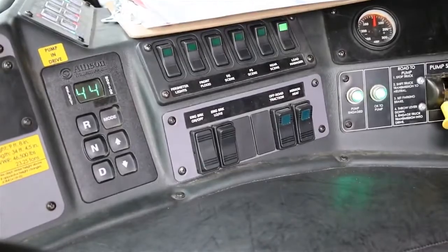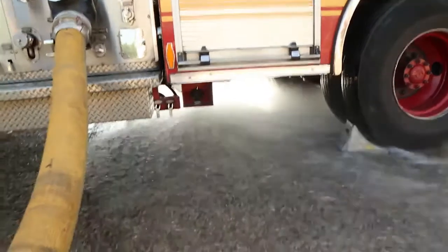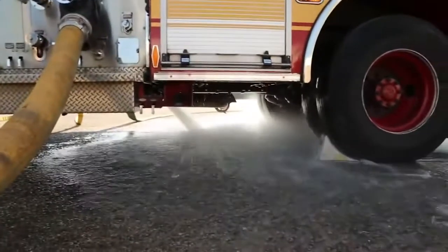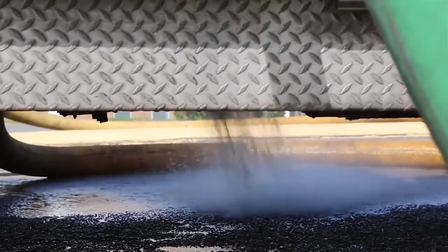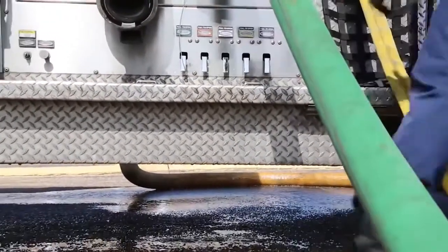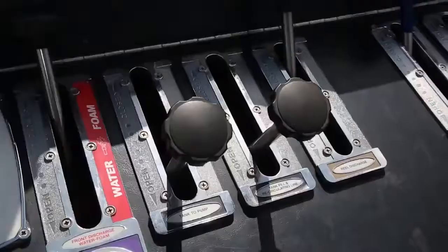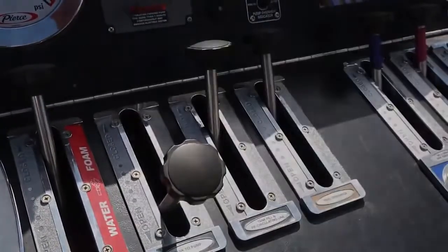Water coming from the bottom of the engine can signify a problem that needs to be remedied. A lot of water coming out under a lot of pressure is indicative of an improperly set intake relief valve. When this occurs, adjust the relief valve to the proper setting. A little bit of water coming out under pressure means there is an open drain valve. Simply close the valve. A lot of water coming out under a relatively lower pressure means your tank is full, but your tank refill is still open. If this is not intended, close your tank refill.